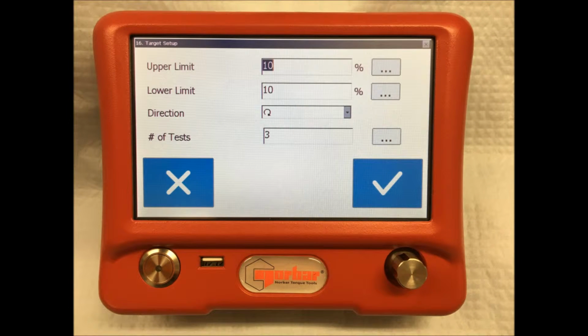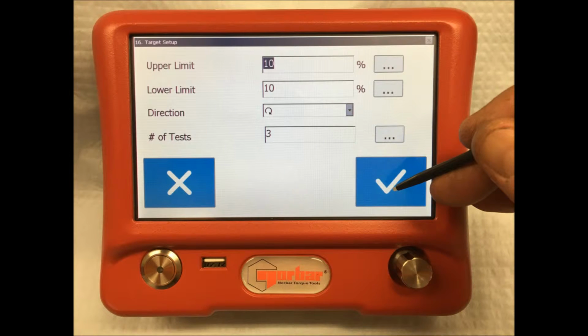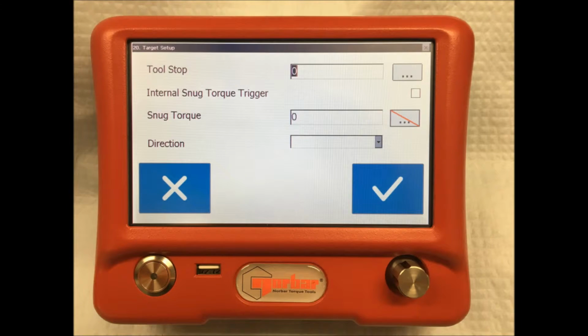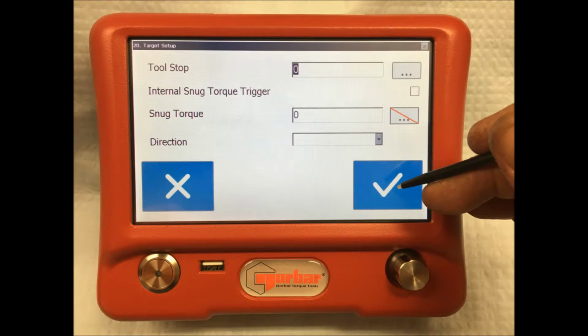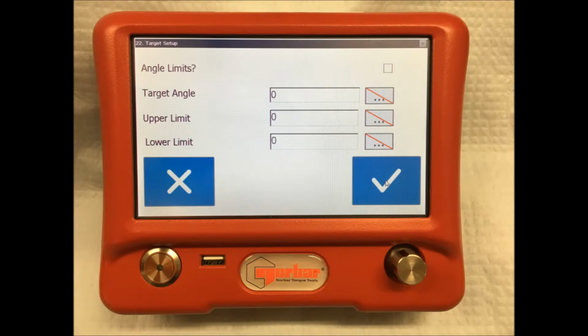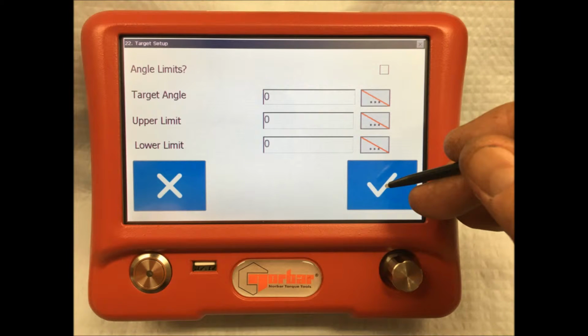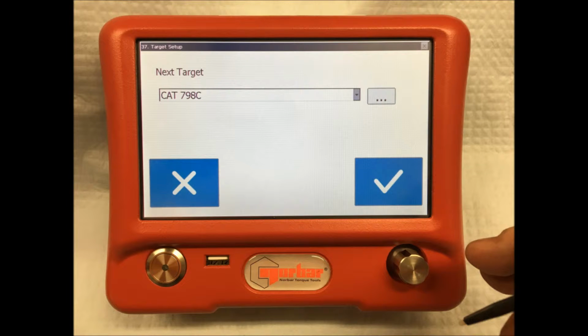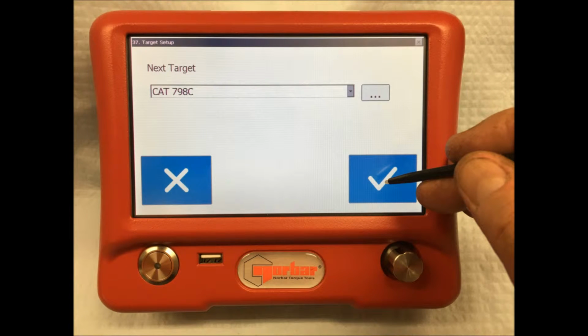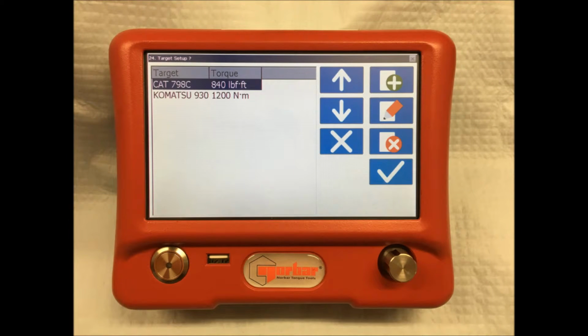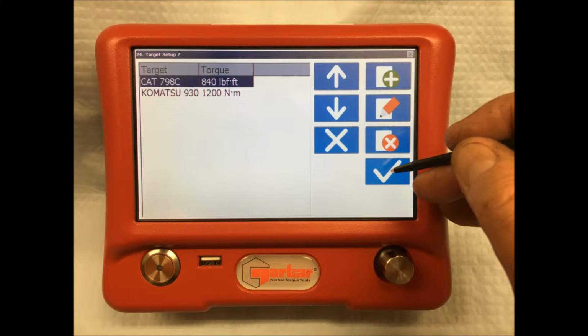It'll take you to another screen which will ask you to set up the upper and lower acceptable variance limits, as well as the direction of rotation and the number of tests you would need to do to get the required result. There are additional screens requesting details for snug torque and angle applications, but these are not necessary for the CAT 798C template. Once these screens are bypassed, the final target can be accepted. The screen will return to the main template screen, where you can then select the CAT 798C template that you have just set up. It will then take you back to the home screen where you can begin testing.